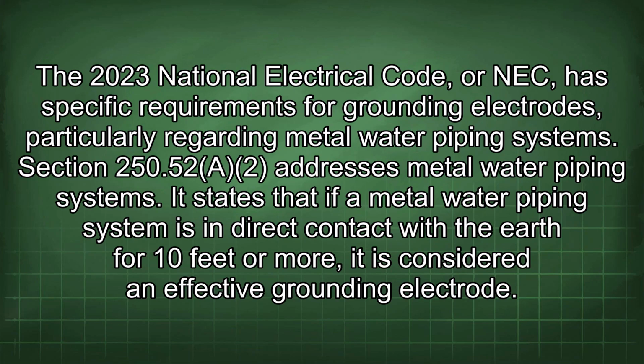The 2023 National Electrical Code, or NEC, has specific requirements for grounding electrodes, particularly regarding metal water piping systems. Section 250.52(A)(1) addresses metal water piping systems. It states that if a metal water piping system is in direct contact with the earth for 10 feet or more, it is considered an effective grounding electrode.